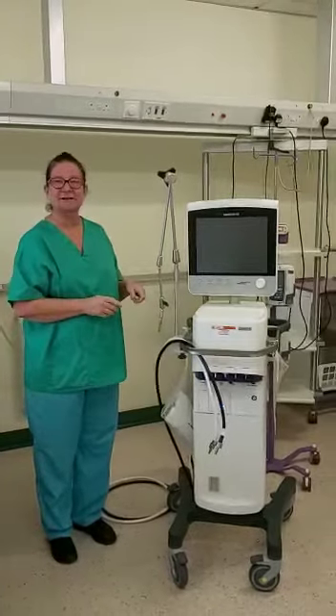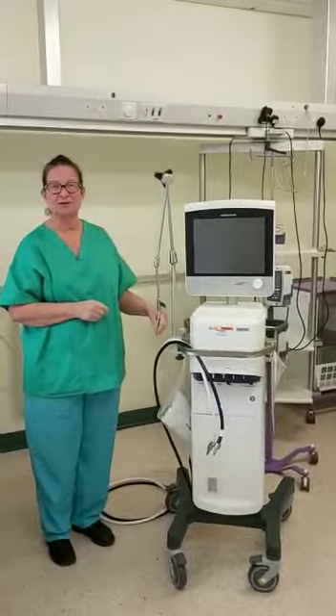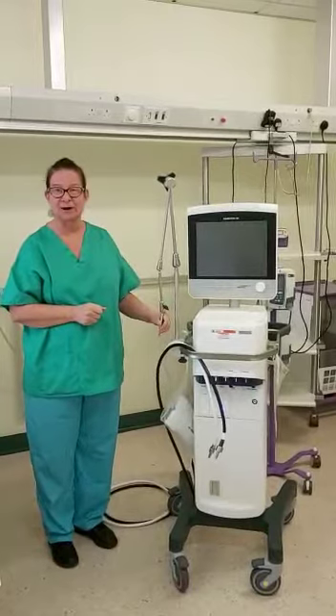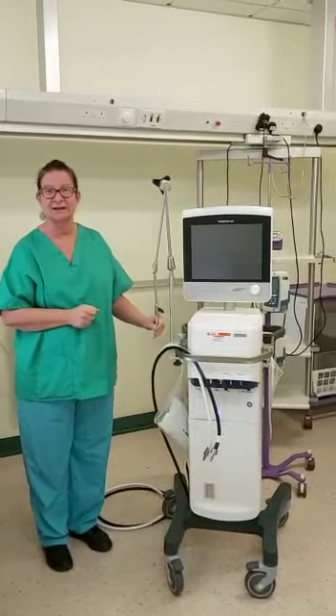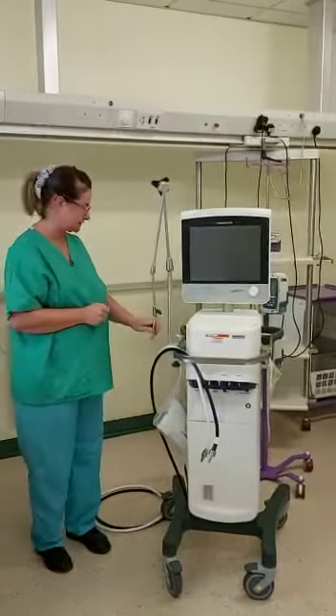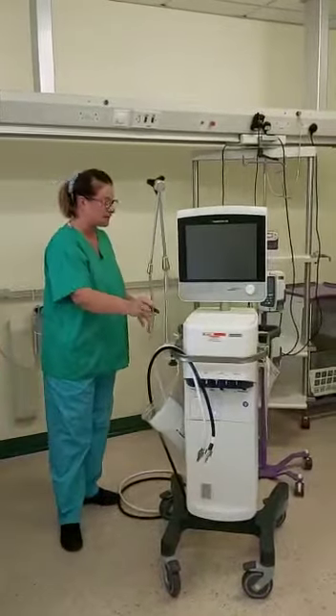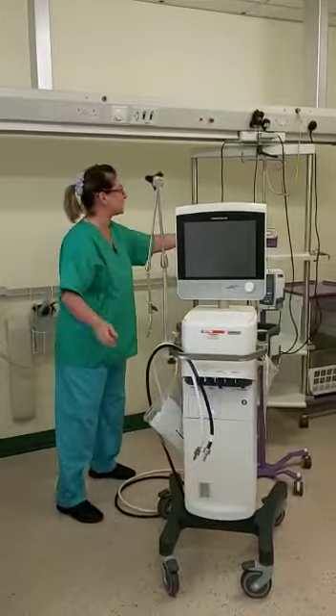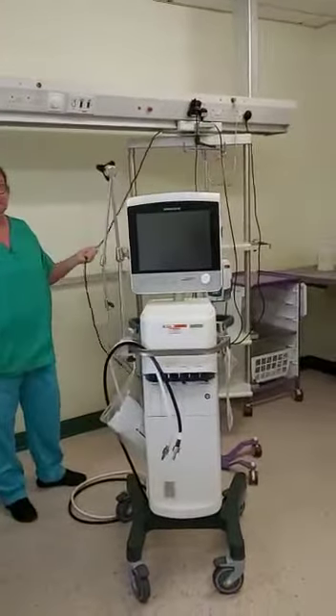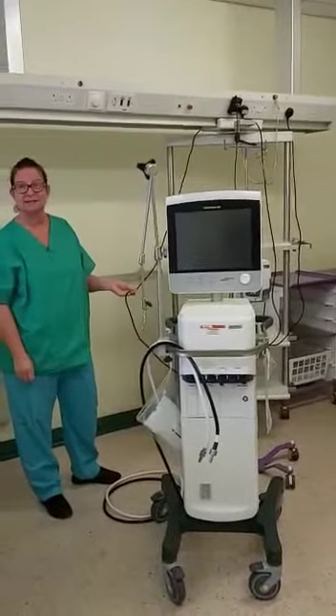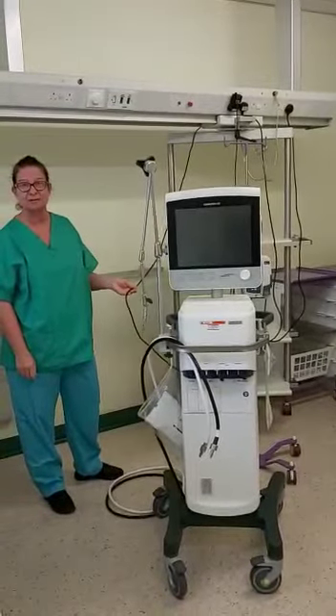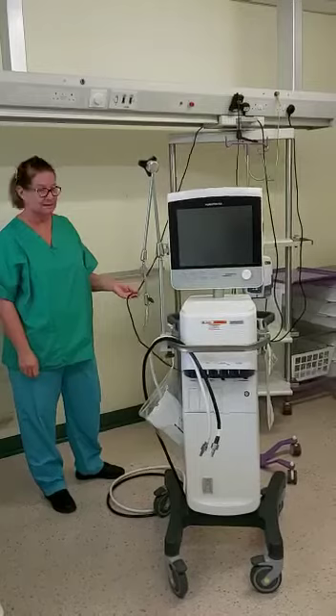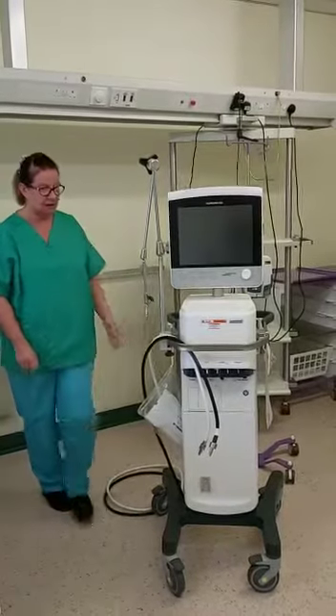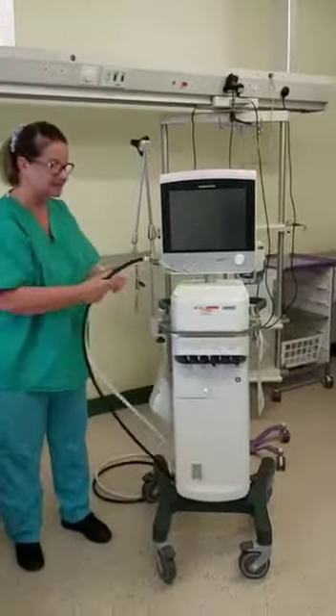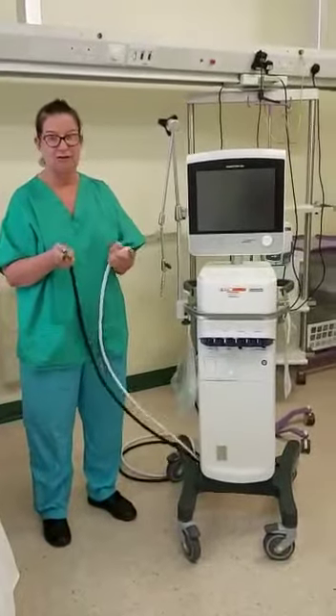So this short video is going to demonstrate how to set up and calibrate the Hamilton G5 ventilator ready for use for your patient. The Hamilton G5 requires a mains supply. It does have a battery backup, but the ventilator should be left plugged in at all times so that battery is constantly charged. You'll also need a gas supply, which comes from air and oxygen.